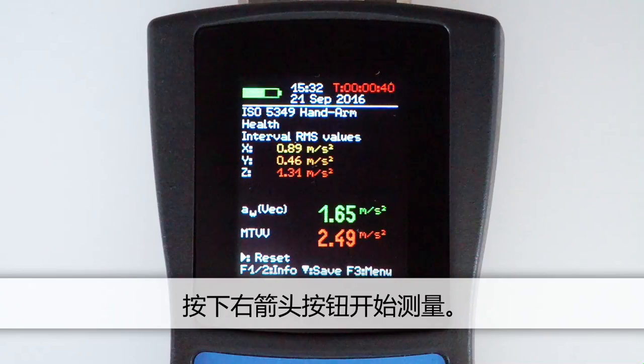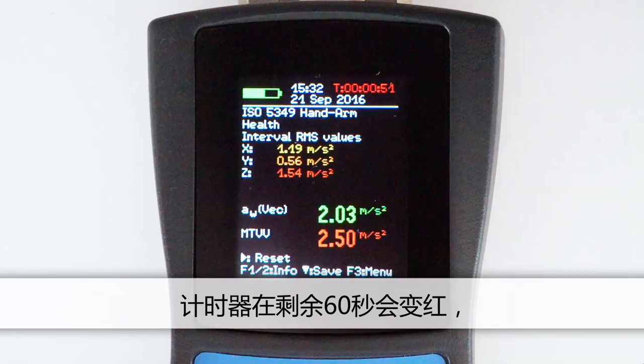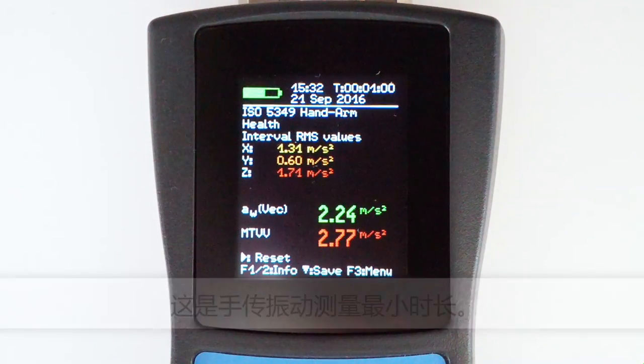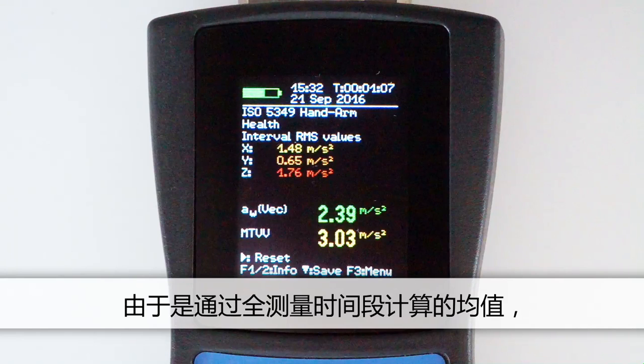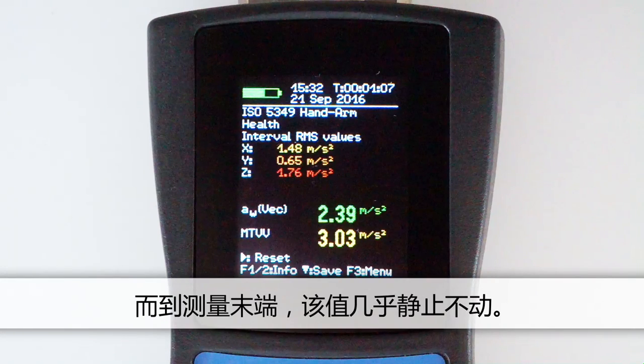Now the measurement can begin. The hands of the test person should be located at the handle of the running machine. Press the right arrow button to start the measurement. In the upper right corner, a timer displays the measurement duration. The timer will remain red for up to 60 seconds, which is the minimum measurement duration for hand-arm vibration. It is nevertheless important to always measure long enough to obtain a representative value of the work process. Towards the end of the measurement, the values should scarcely change.